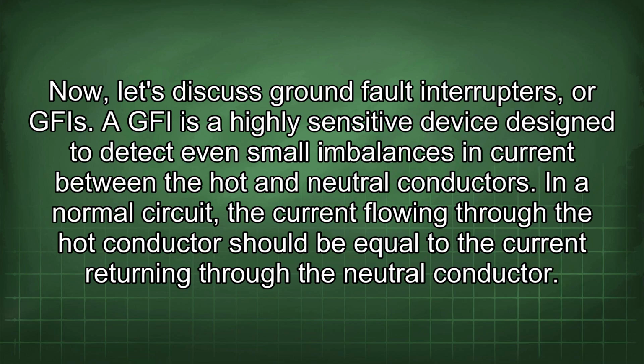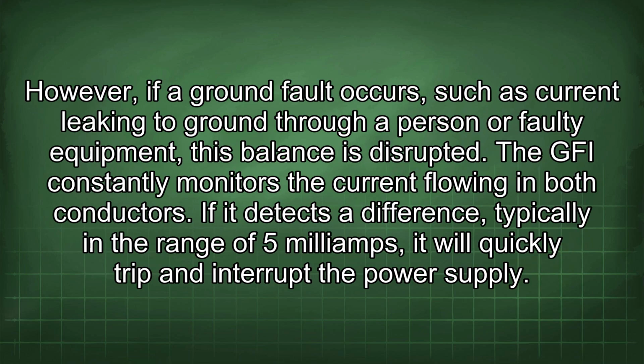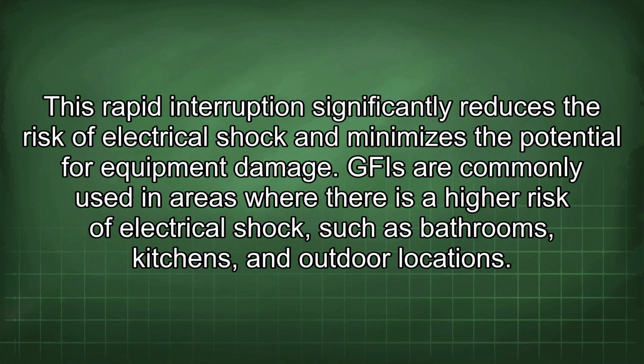A GFI is a highly sensitive device designed to detect even small imbalances in current between the hot and neutral conductors. In a normal circuit, the current flowing through the hot conductor should be equal to the current returning through the neutral conductor. However, if a ground fault occurs, such as current leaking to ground through a person or faulty equipment, this balance is disrupted. The GFI constantly monitors the current flowing in both conductors. If it detects a difference, typically in the range of 5 mA, it will quickly trip and interrupt the power supply. This rapid interruption significantly reduces the risk of electrical shock and minimizes the potential for equipment damage.